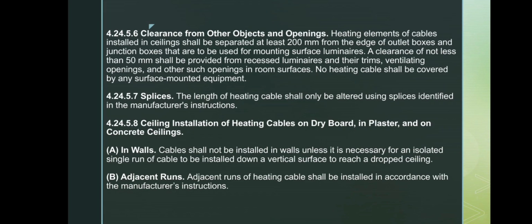Next, we look at the clearance and installation rules for heating cables in ceilings. Heating cables must be kept 200 mm away from the edge of outlet or junction boxes used for surface mounted lights. They also need at least 50 mm clearance from recessed lights, vents, or similar openings. No heating cable should ever be covered by surface mounted equipment. For splicing, heating cables can only be altered using manufacturer-approved splices. In ceiling installations, cables must not be placed inside walls unless it is just a single run that must pass vertically to reach a drop ceiling. Adjacent cable runs must always follow the spacing provided in the manufacturer's instructions.